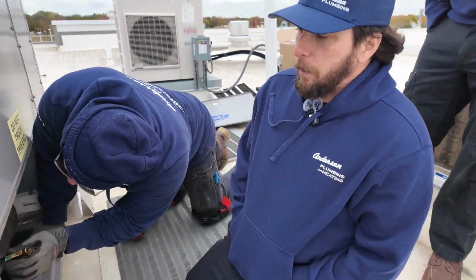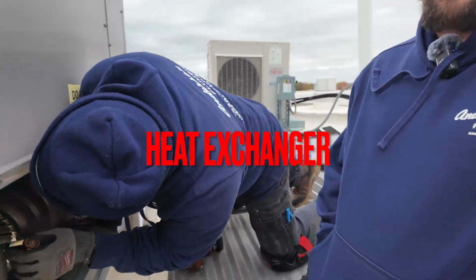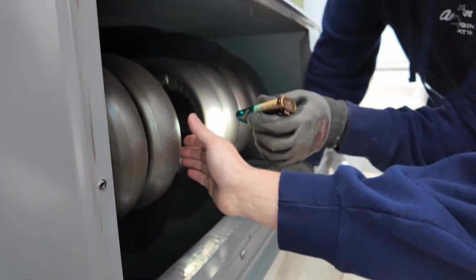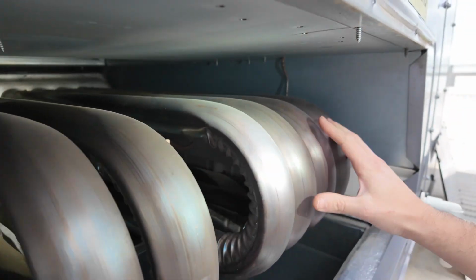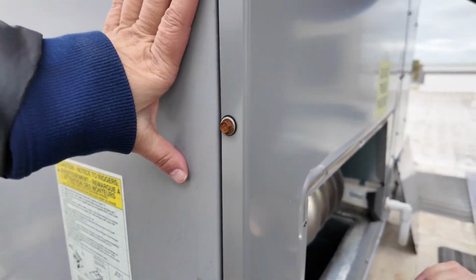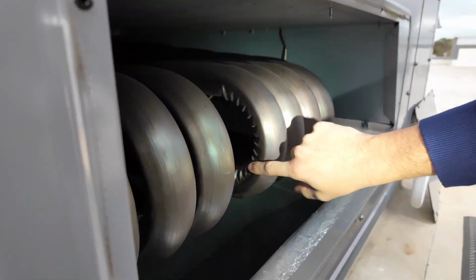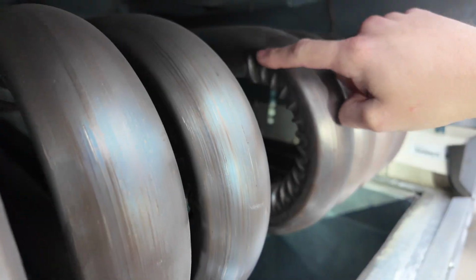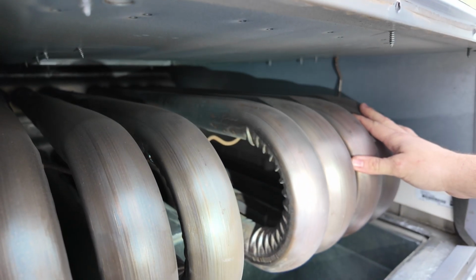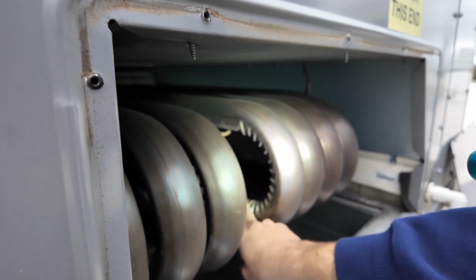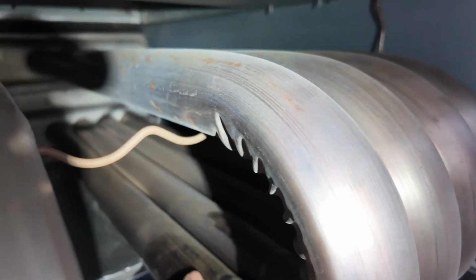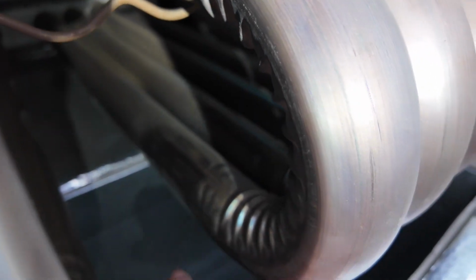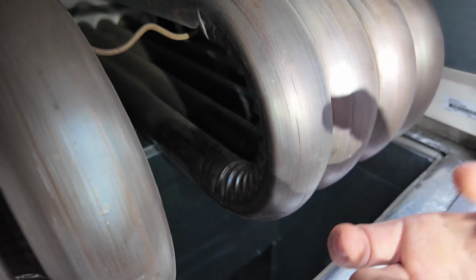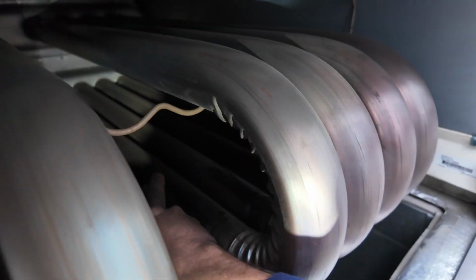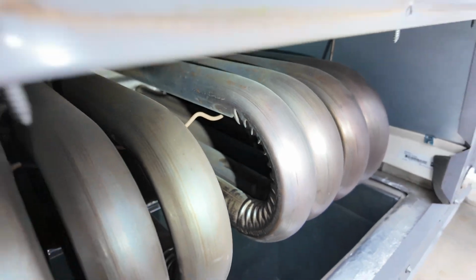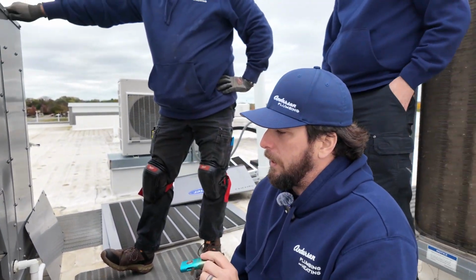One of the other super important pieces that we inspect on these units is what's called the heat exchanger. This is the heat exchanger that you're looking at here. This is the series of tubes. One of the things that we're looking for in the most common failure points is right on these corners where these bends are made. These tubes start out life as a straight piece of tubular steel. They are a seamed tube. If you see that seam right there, basically they start life as a flat piece of metal and then it's rolled over and welded. So those seams are also a super common failure point because that's where the pipe was fused together originally.